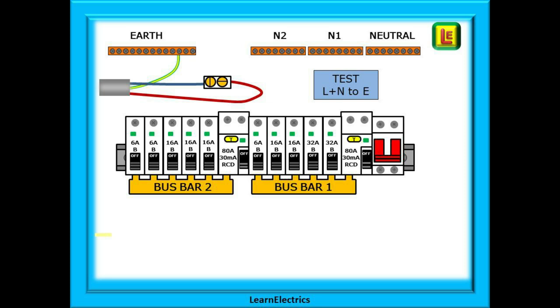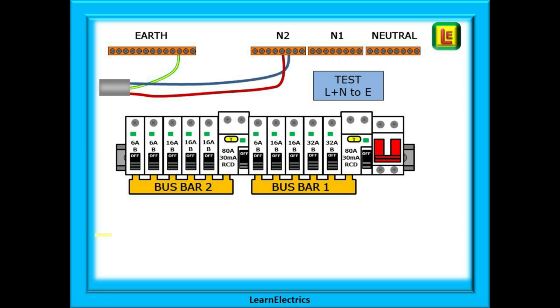This is one method of connecting line and neutral together: remove the line from the MCB, the neutral from the neutral bar and connect them together with a connector block. Your meter probe will make contact with the brass screw in the connector block and the other probe can go onto the earth bar. Another method of connecting line and neutral together removes the phase or line conductor from the MCB and places it into a spare hole on the appropriate neutral bar.